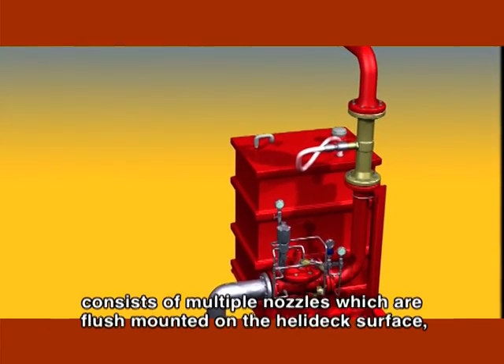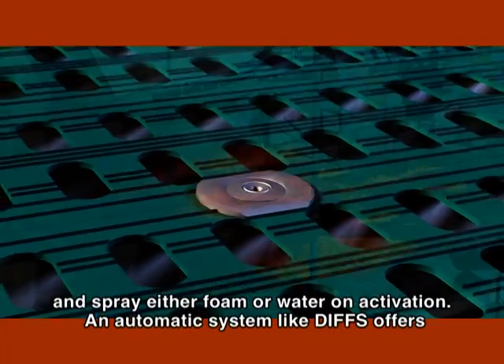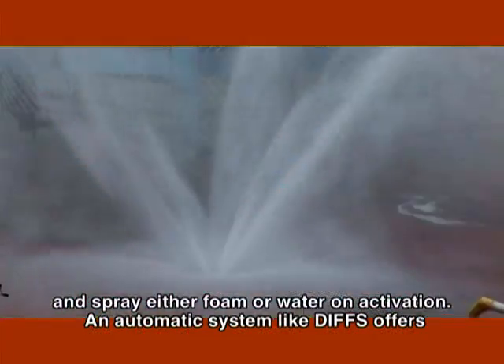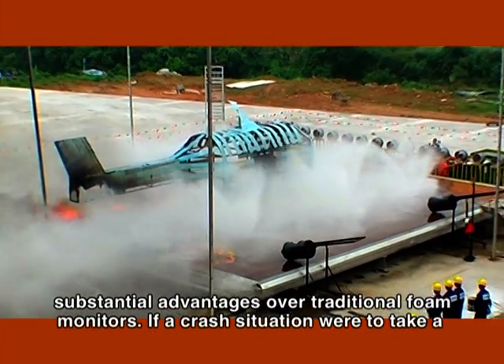A DIFFS unit consists of multiple nozzles, which are flush-mounted on the helideck surface and spray either foam or water on activation. An automatic system like DIFFS offers substantial advantages over traditional foam monitors.